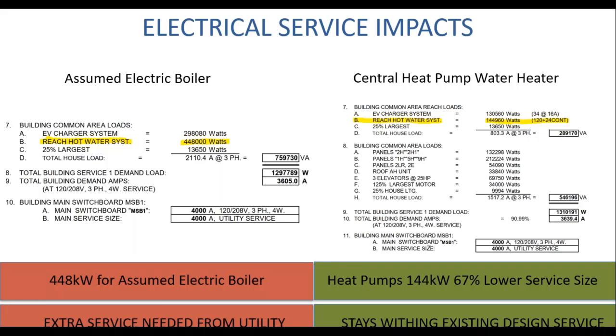What we're talking about is a heat pump strategy with storage. They said, oh, okay. So we went out to the manufacturers, and that load dropped to 144 kW. This is a really large apartment building, over 100 units, so significant. That stayed within their service size and dropped down the electrical connections and the cost of the systems. So, one strategy.